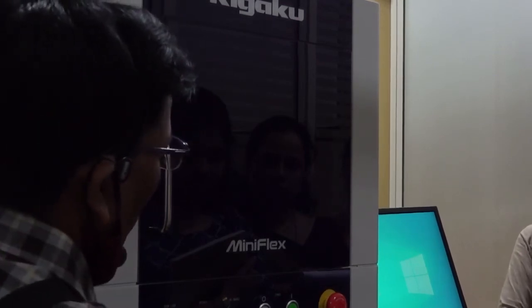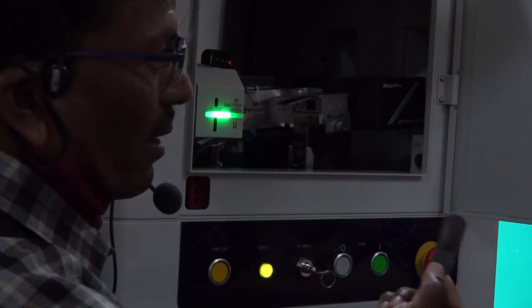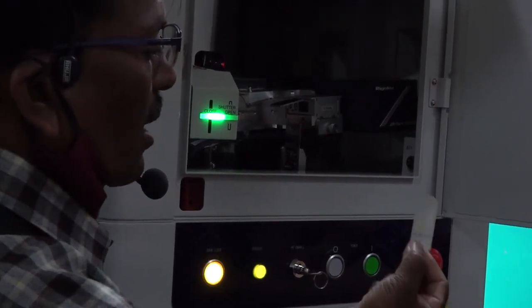You start the instrument. This is the off button. This is the on button. So you have to start it. Here inside you can see the computer. And this one is the X-ray source, a copper X-ray source. Here one shutter is there, and a Soller slit is there to avoid the scattering of the X-rays. So X-rays will come out from here. It will fall on your sample. This is your sample. It will reflect and again pass through the receiving Soller slit.